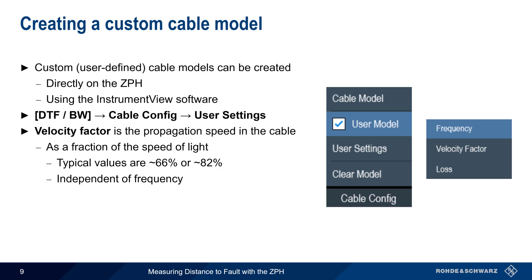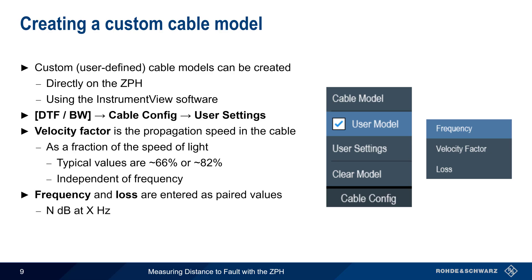The velocity factor value is independent of frequency. The cable loss, or attenuation, is specified as paired values of frequency and attenuation — that is, N dB at X Hertz. The ZPH will interpolate between entered values. When done, press User Model to apply the settings.